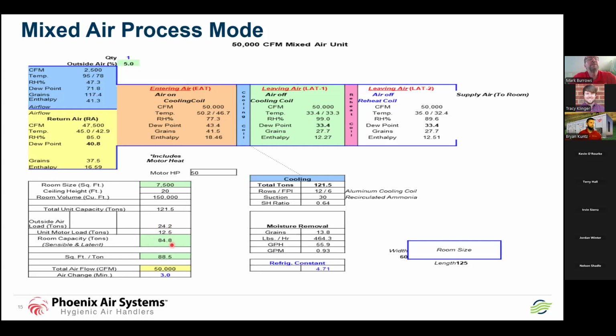And what that means is we get about 88.5 square foot per ton. The safe range is typically 100 square foot per ton. And all we're doing, you look at your room size at 7,500 divided by what's available for the room. In this case, 84.8, and you're left with 88.5 square foot per ton. Typical stuff, a little bit on the conservative side, but it would certainly work. And then look at that air change down below at a 3-minute air change.